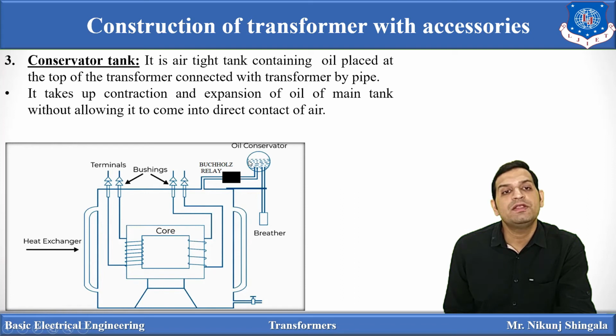The function of the conservator tank is to take the contraction and expansion of the oil, but without allowing it to come into direct contact with the air. If oil comes into direct contact with the air, then it loses its property in a very short time. If oil loses its property in a short time, then there may be a short circuit in the tank. That's why the conservator tank is placed on the top of the tank.